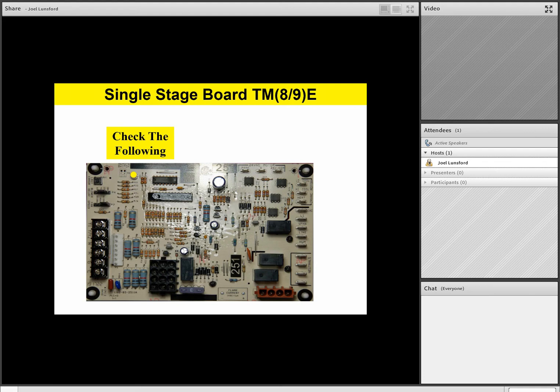So normal operation gives us a slow yellow or amber flash, but it also tells us that we have a call for heat, and the board has also gone out and double checked its own electronics, so it's passed its internal check. We have a call for heat, and it's operating normally. So a slow amber flash is what it should have when it's working properly.